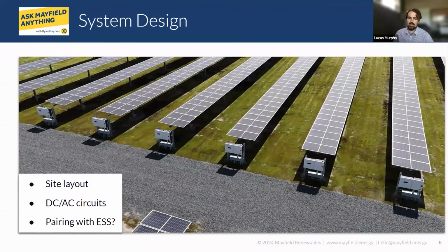A lot of this decision comes down to AC and DC losses, right? So we found that DC voltage drop and DC losses are less expensive than AC voltage drop.